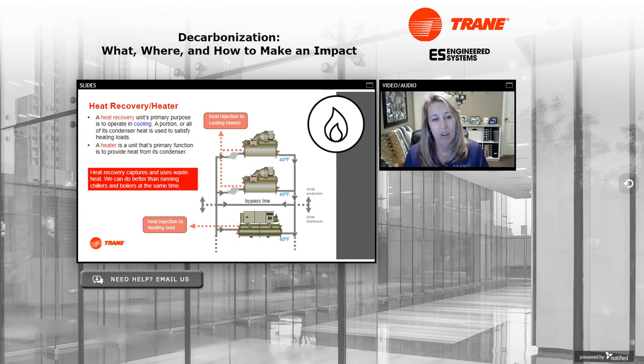We can do better than running a boiler and a chiller at the same time. Within large buildings, we typically have a heating and cooling load all year long. So we can move or export heat from the warm interior of the building and utilize that in the cold exterior of the building, really using that heat energy that we previously would have rejected as waste to reduce our heating load. By doing this, we're reducing our heating load, we're saving money, and we're also helping to reduce our carbon footprint.